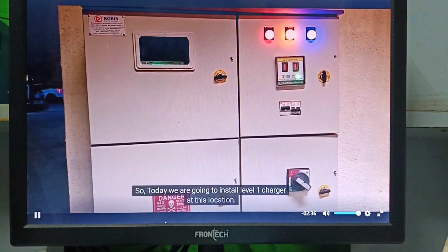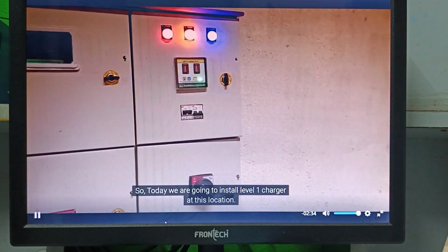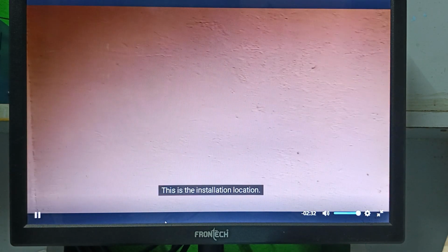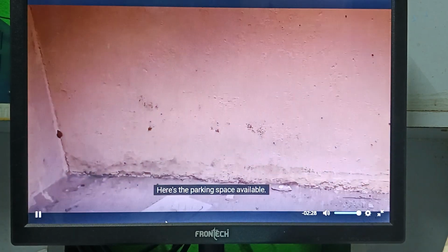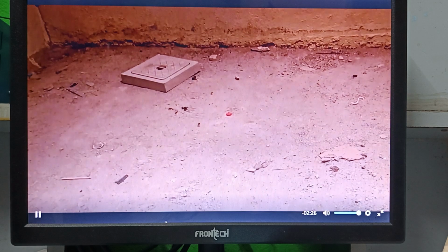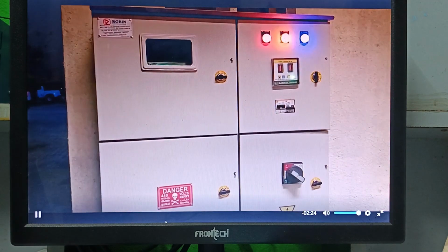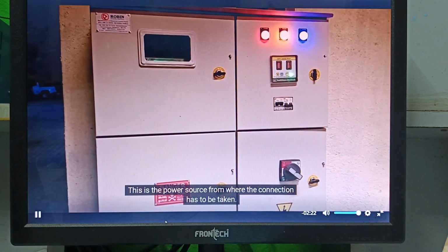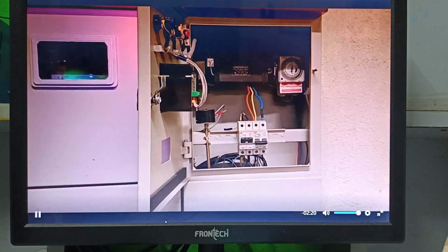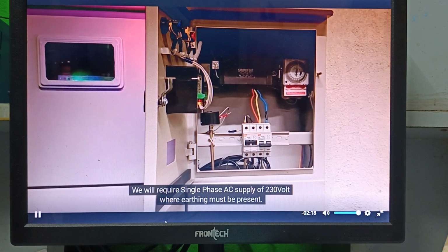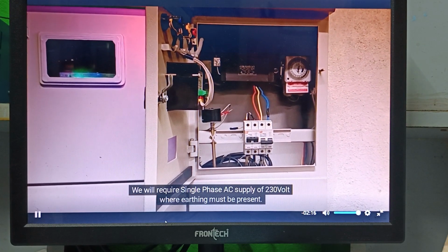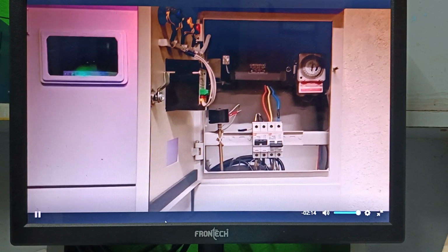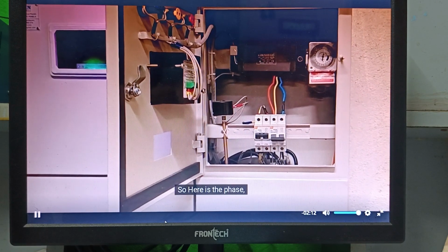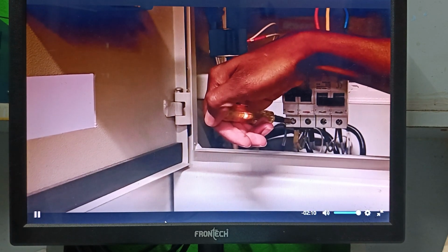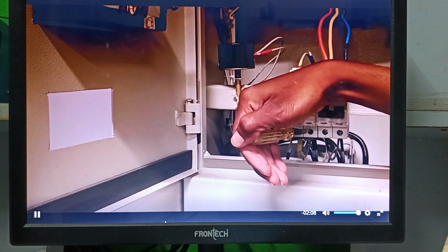So, today we are going to install a Level 1 charger at this location. This is the installation location. Here is the parking space available. This is the power source from where the connection has to be taken. We will require a single-phase AC supply of 230 volt where earthing must be present. So here is the phase, neutral, and earthing.